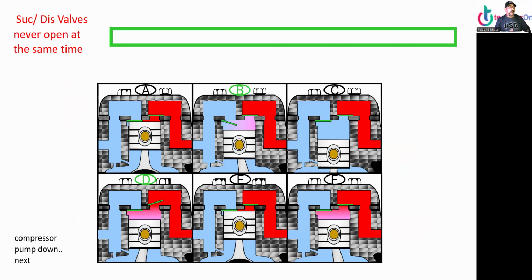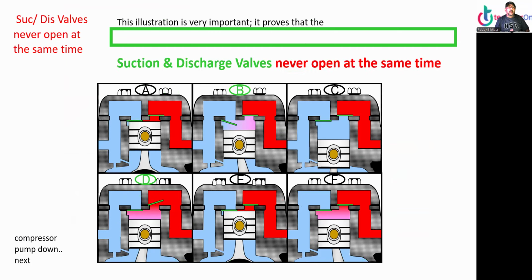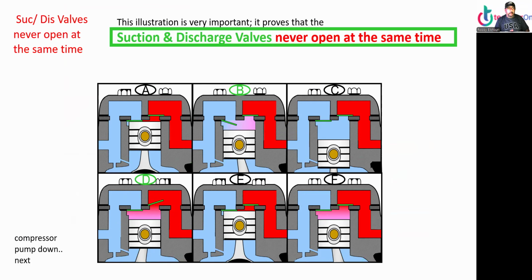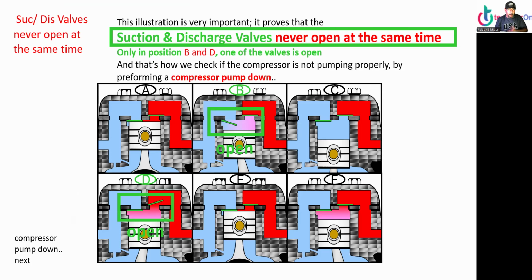Alrighty. Now, so okay, let's move on now. Suction and discharge valves never open at the same time. It's very important. This illustration is very important. It proves that the suction and discharge valves never open at the same time. Only in positions B and D is one of the valves open. As you can see, look at all these valves. Only B and D, one of them is open. So any time the compressor shuts off, you never have bypass from high to low. And that's how we do compressor pump downs next. That's how we check if the compressor is not pumping properly, by performing a compressor pump down.